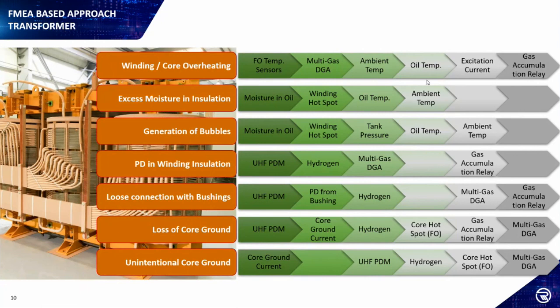And where our customers today are running into another problem is installing every sensor to predict that failure mode. If I just talk about the winding and core overheating issue, this can be detected by installing fiber optic temperature sensors on the winding and core. It can also be detected by multi-gas DGA or oil sampling, ambient temperature, oil temperature, excitation current, gas accumulation relay. All these sensors are used for predicting this failure mode, which is winding and core overheating. But if I talk about a minimal sensor, only a fiber optic temperature sensor installed on the windings is more than sufficient to predict this failure mode.